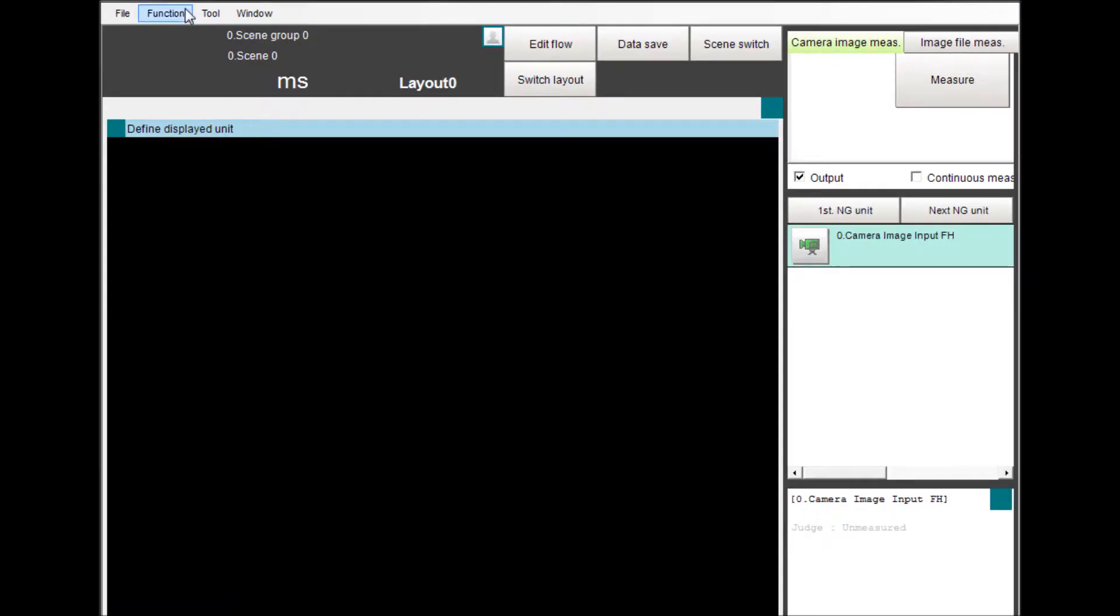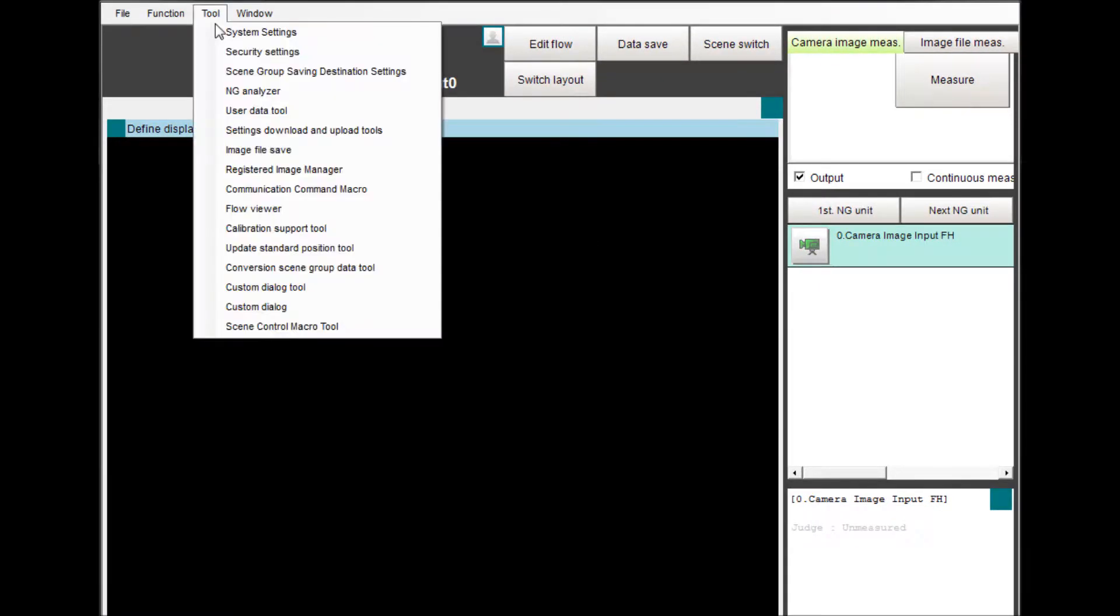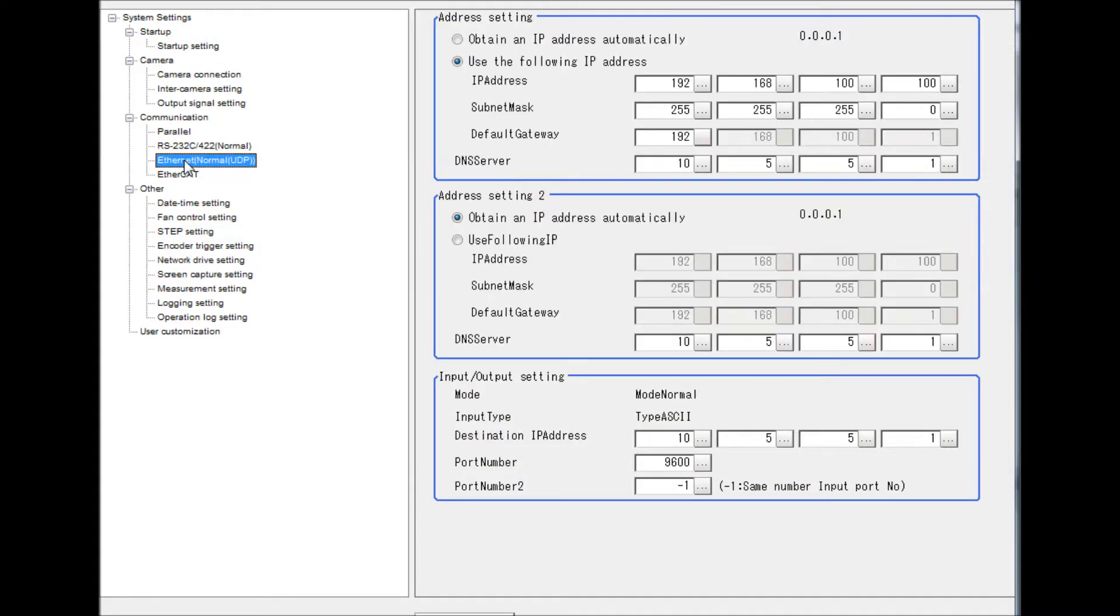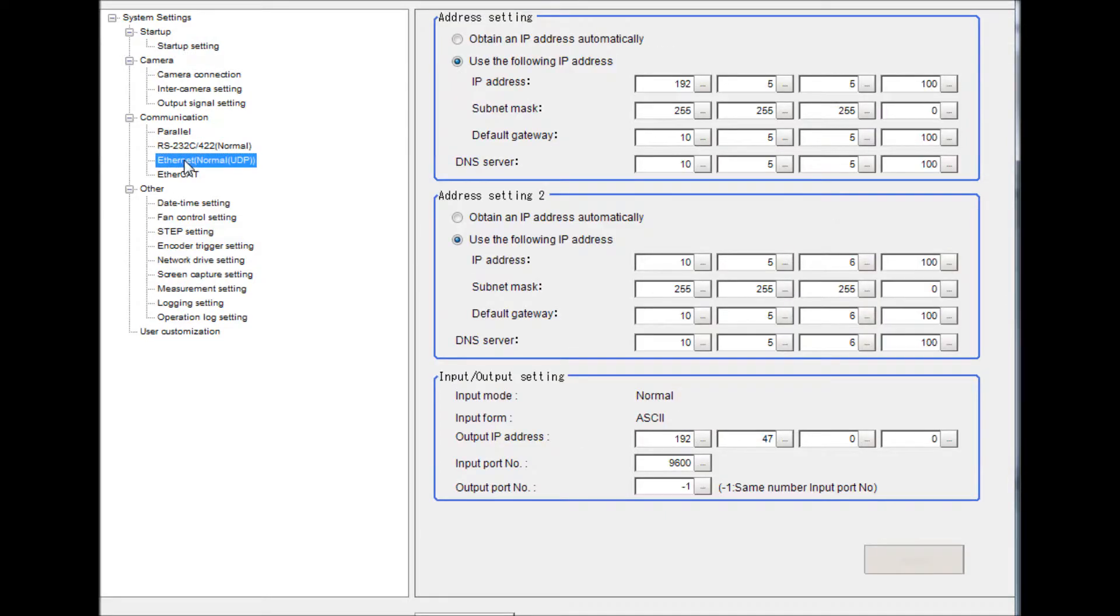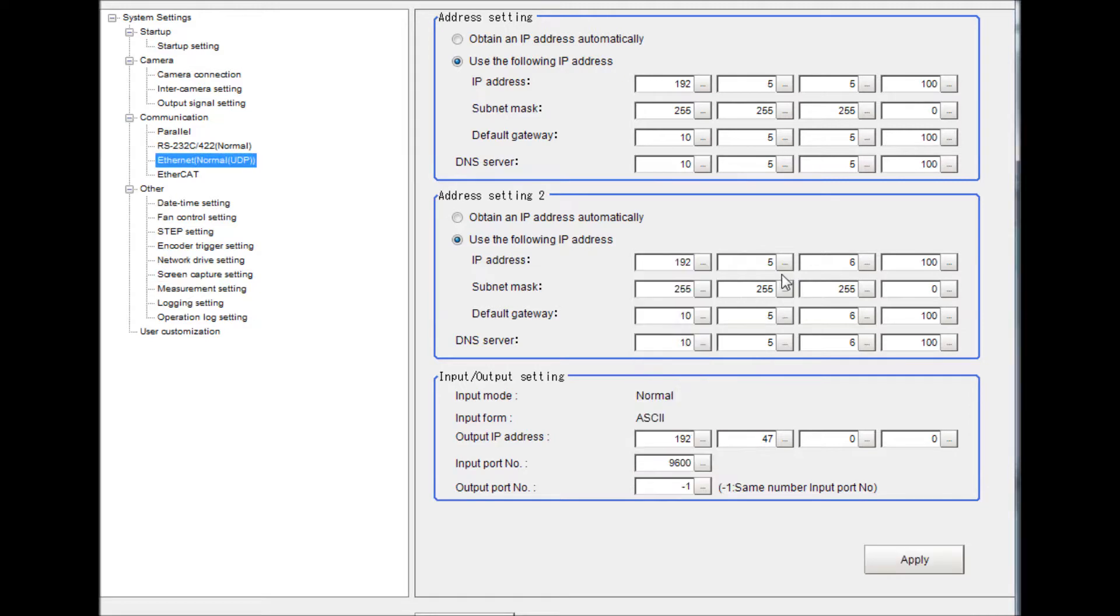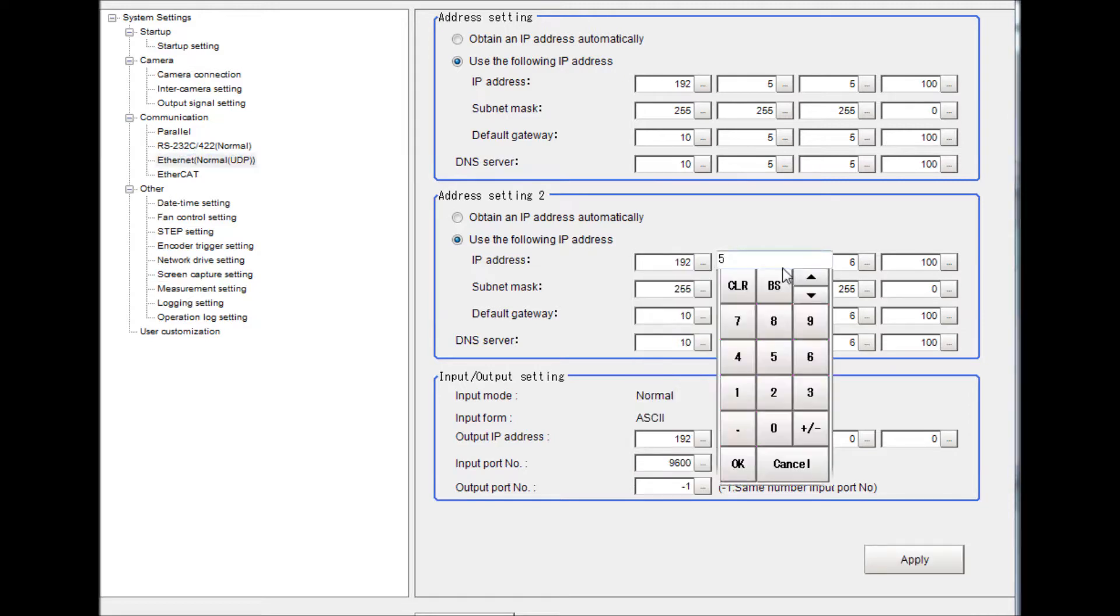From the menu, select Tool and System Setting. On the right side, under System Setting, then select Communication. Select Ethernet Normal UDP and go to the Use the following IP Address option for setting number 2. Enter your IP address. To do this, select the button to the right so a numerical pad appears.